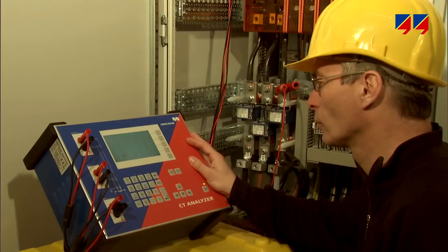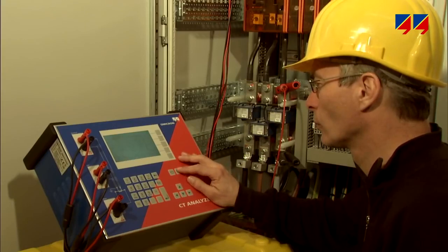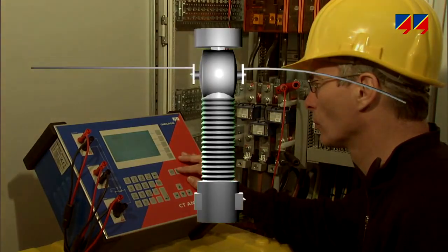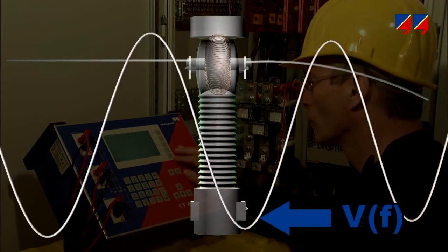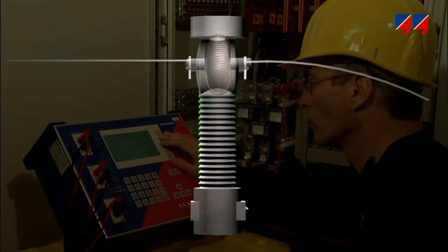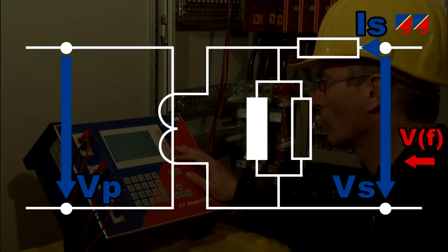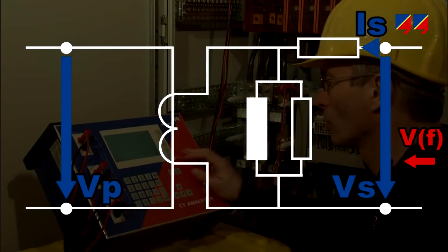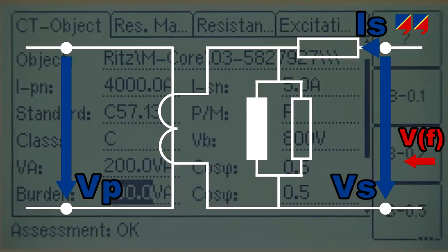CT Analyzer allows the limitations of the various traditional methods to be overcome. It opens the black box through secondary injection with variable frequency, and a patented low-voltage, low-frequency method for excitation measurement. It identifies all the parameters of the CT equivalent circuit diagram, and thus accurately determines the CT's behavior for protection and metering applications.